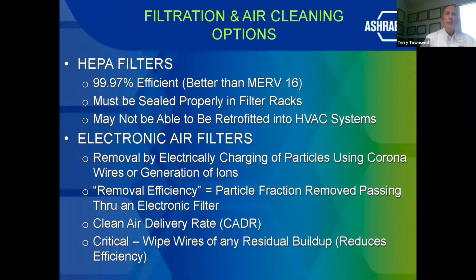Now, if we look at HEPA filters, they are 99.97% efficient. And a MERV 16 is the highest efficiency that you can get without going to a HEPA. But the HEPA filters have to be sealed properly in the filter rack so that you do not have bypass. And some may not be able to be retrofitted. So that's why you have to get with the equipment supplier or manufacturer and see what can be done.